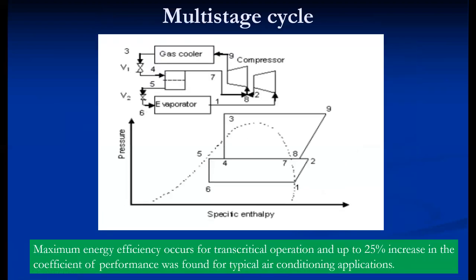The third cycle is multi-staging. Multi-staging is especially used when the system demands higher temperature limits — mainly when the CO2 refrigeration system is used for refrigeration applications, because refrigeration handles lower temperature limits than air conditioning applications. Due to multi-staging, the point shifts towards the left — from where it arises in simple systems to point number six — and there is almost 25% saving of energy, or a 25% increase in the coefficient of performance. Multi-staging also saves energy, so a significant improvement in COP happens in this case.